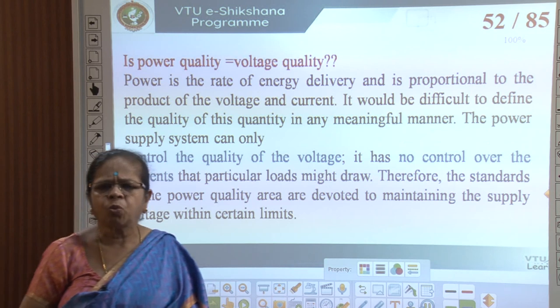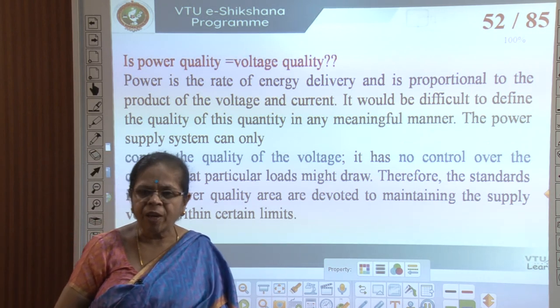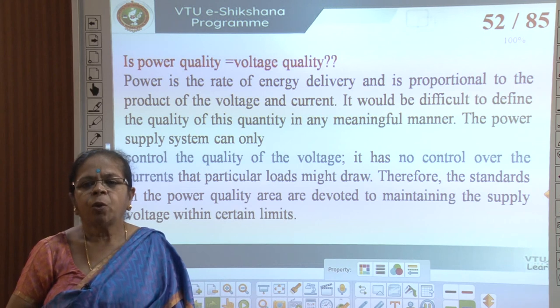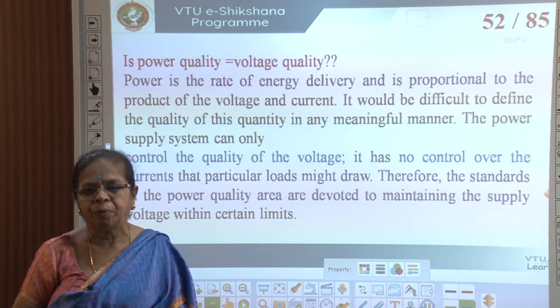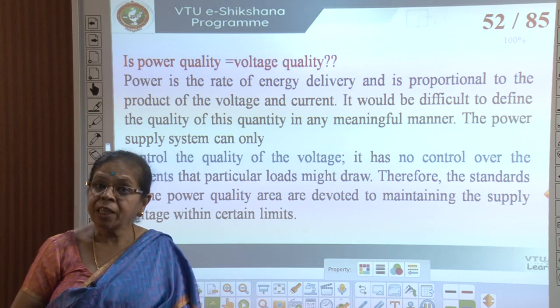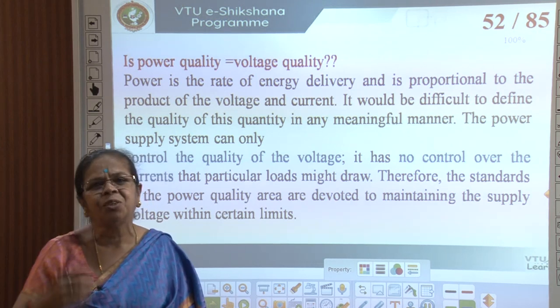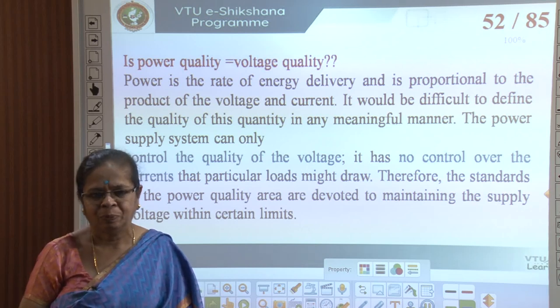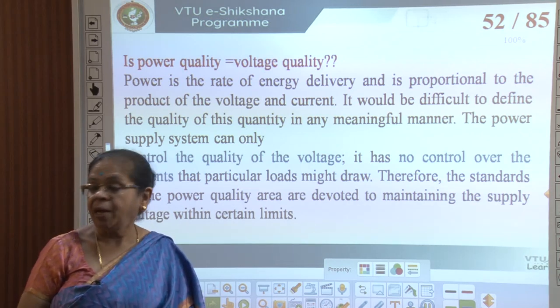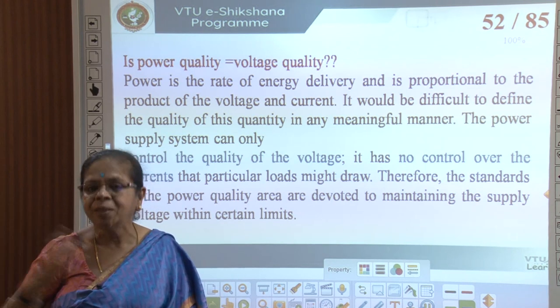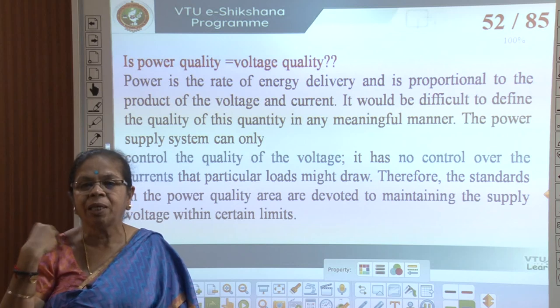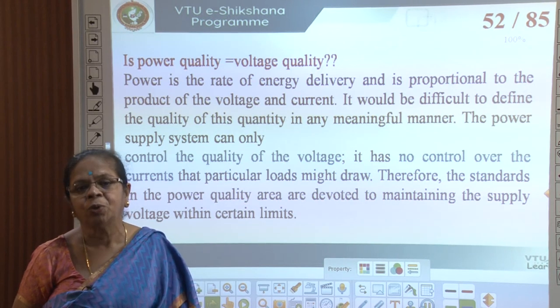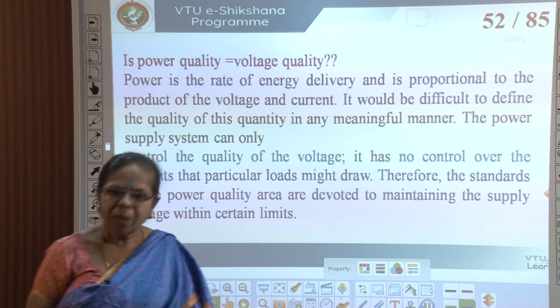Is power quality the same as voltage quality? Yes. Power is the rate of energy delivery and is proportional to the product of voltage and current, so it would be difficult to define power quality in a meaningful manner. The utility can only control the voltage — it cannot control the power, which is determined by the load — so the utility has no control on load currents. Therefore, when we say good quality power we mean good quality voltage, because what we get from the utility is the voltage, and the current drawn depends on what load we connect. Power quality means voltage quality.